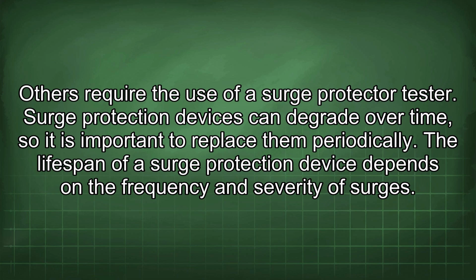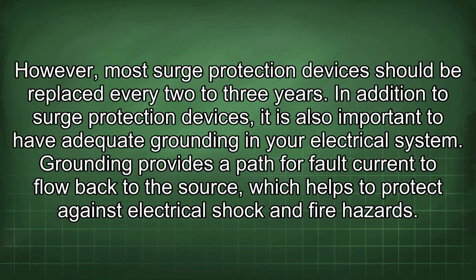Surge protection devices can degrade over time, so it is important to replace them periodically. The lifespan of a surge protection device depends on the frequency and severity of surges. However, most surge protection devices should be replaced every 2 to 3 years.